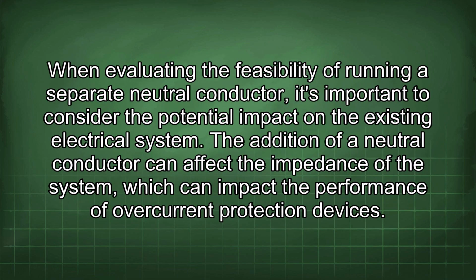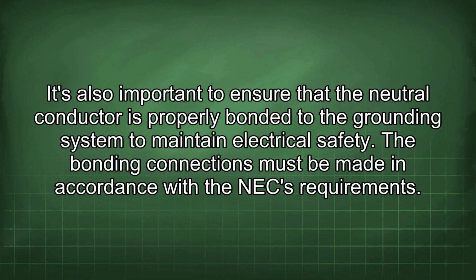When evaluating the feasibility of running a separate neutral conductor, it's important to consider the potential impact on the existing electrical system. The addition of a neutral conductor can affect the impedance of the system, which can impact the performance of overcurrent protection devices. It's also important to ensure that the neutral conductor is properly bonded to the grounding system to maintain electrical safety. The bonding connections must be made in accordance with the NEC requirements.